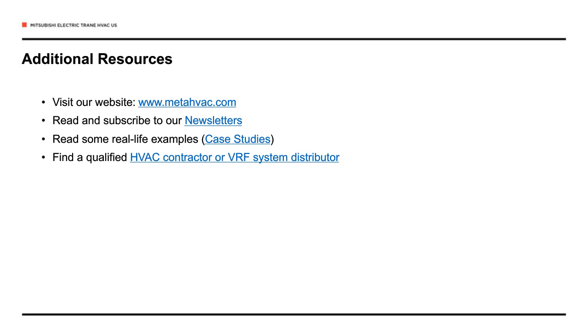In that case, there were some other considerations on that building design that helped lower the cost. They had boilers up on the 8th floor mechanical room, and they were pumping hot water all the way down to the first floor to serve some wall-fin radiation, which served a big glass curtain wall. So we were able to use our booster units, which is a VRF indoor unit that makes hot water, and eliminate a lot of that piping throughout the building. So there are some other considerations on that project.